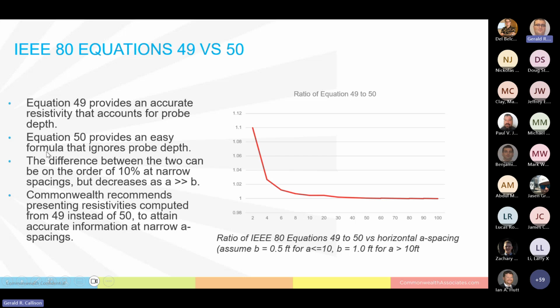Now, equation 49 versus 50. Equation 49 is going to provide a more accurate resistivity because it accounts for probe depths. Equation 50 is quick and dirty, useful if you're looking at formulas and want a sanity check. I've provided a graph that shows differing results between equation 49 and equation 50, assuming a B depth of 1/2 foot for horizontal spacings less than or equal to 10 feet, and 1 foot for horizontal spacings above 10 feet.